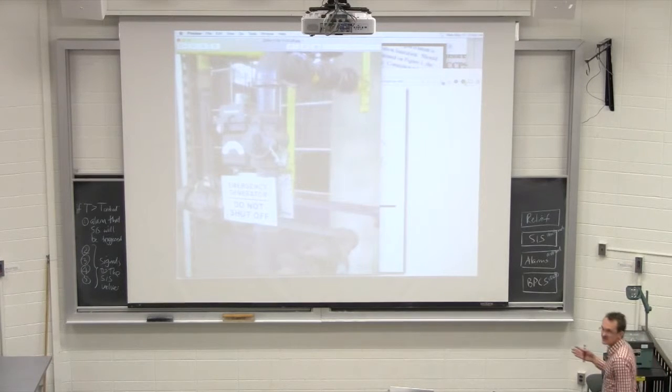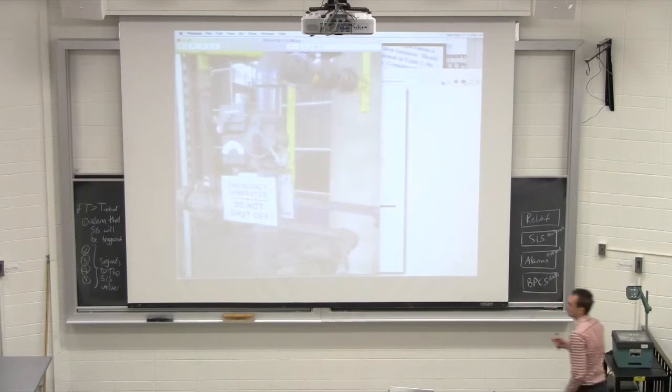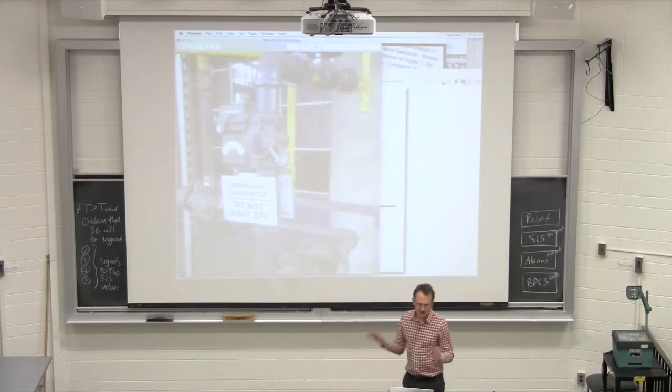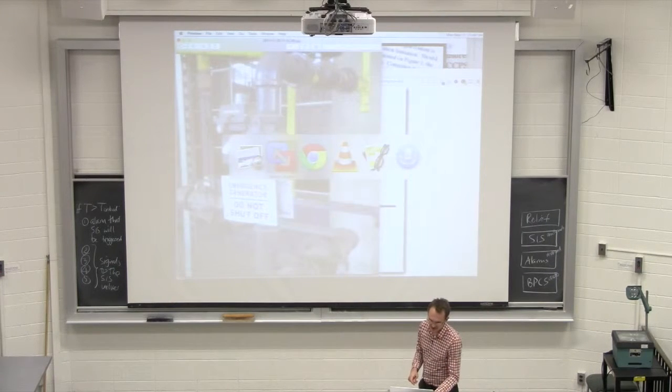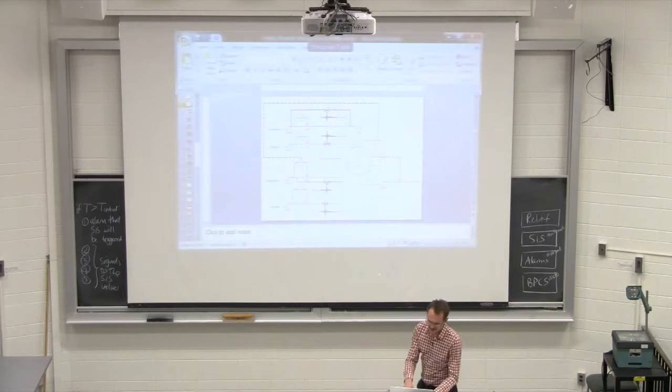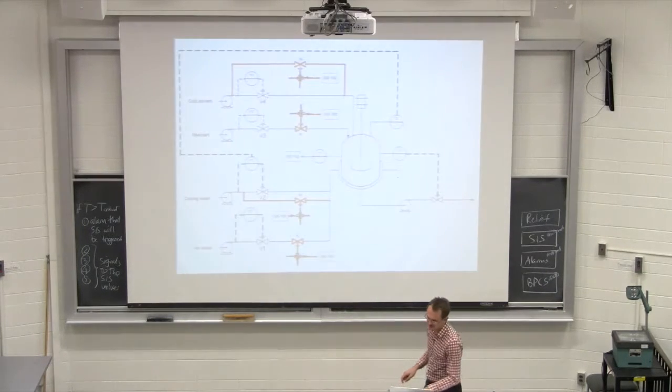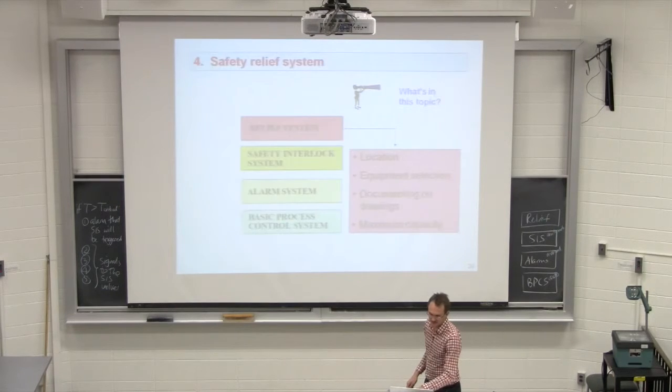So you will see this. I'll guarantee you, in your career, you'll walk past valves that have signs like this: do not turn off, do not turn on. An incident in the United States was caused by exactly one of these incidents occurring, a sign on the valve saying, do not shut off. Right? So a sign does not stop a valve from actually being shut, or a system that normally is open and can be depressurized from being pressurized. So we must provide relief, okay?